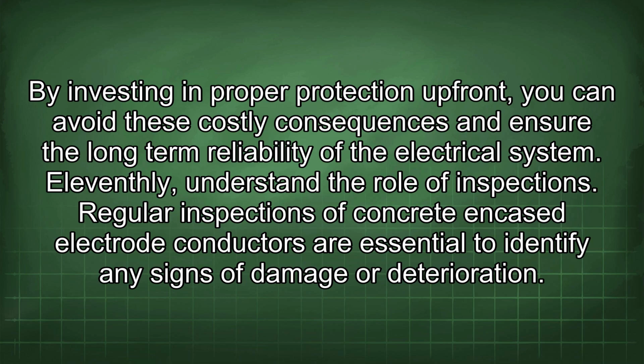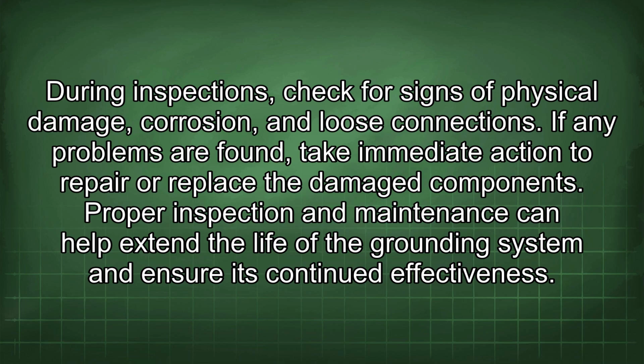11thly, understand the role of inspections. Regular inspections of concrete encased electrode conductors are essential to identify any signs of damage or deterioration. During inspections, check for signs of physical damage, corrosion, and loose connections. If any problems are found, take immediate action to repair or replace the damaged components. Proper inspection and maintenance can help extend the life of the grounding system and ensure its continued effectiveness.